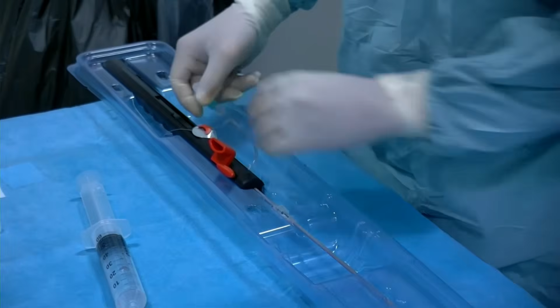We will now retract the device into the sheath in a moment. But before that, I'll just show you that the handle consists of several parts. There's this protection part that comes in the package. Then there's a locking handle, and there's the slider, which we will use to advance and retract the device from the sheath. So first step will be to secure that the connections are tight, and for easy injections, we'll just add this 3-way tap.